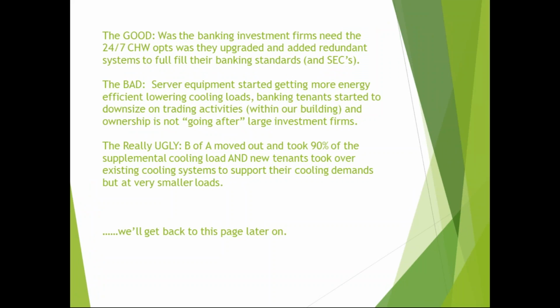Now the really bad is when one tenant took out 90% of the supplemental cooling load. So that 175, 225 now went down to 60 — I don't know if that's the right math, but somewhere around there, 60, 50 tons. So now all that infrastructure I showed before, the big chilled water systems and the big condenser water pumps, those have to stay on. Are you kidding me?